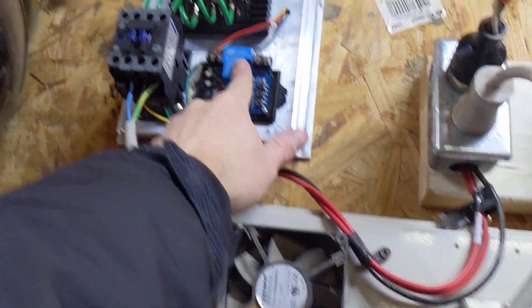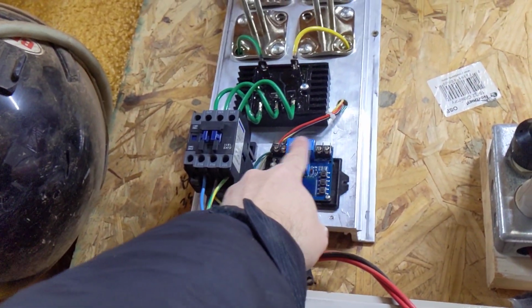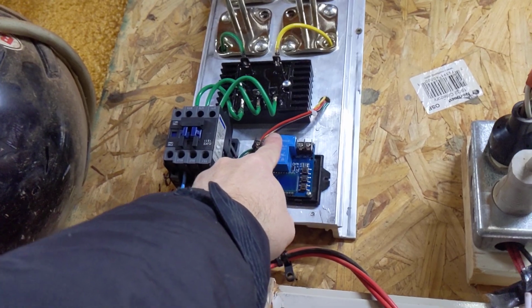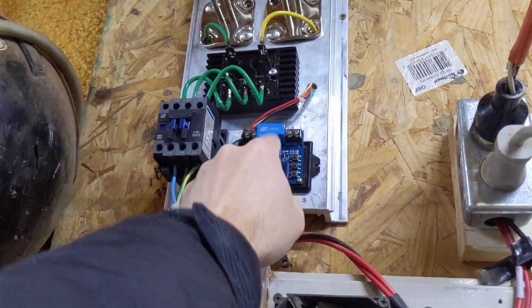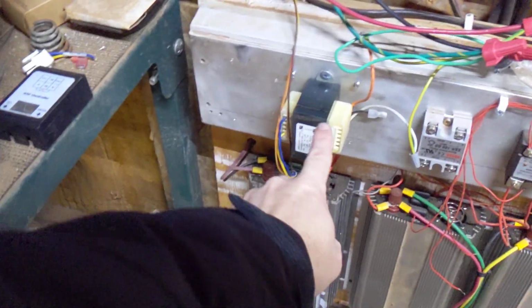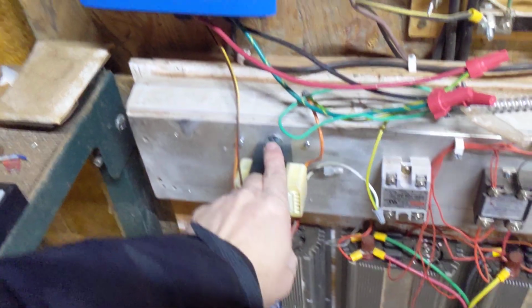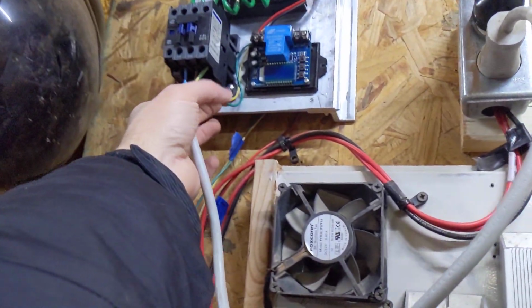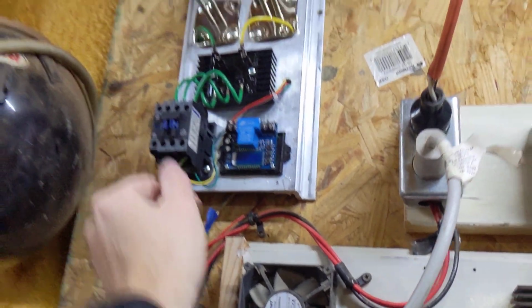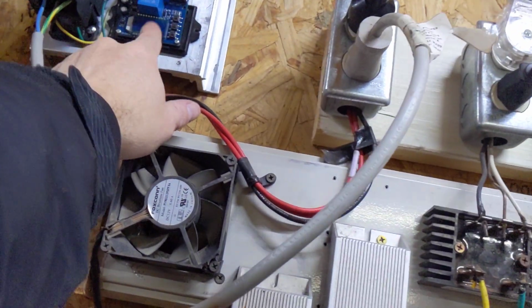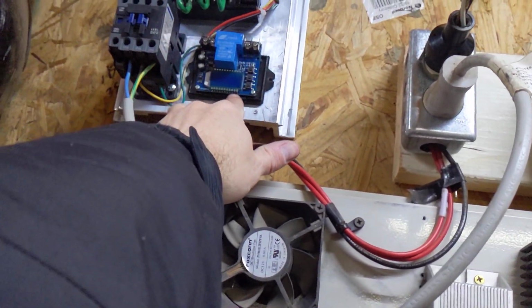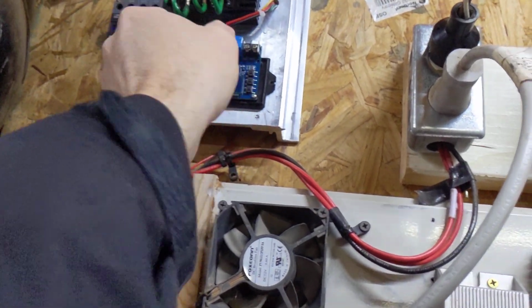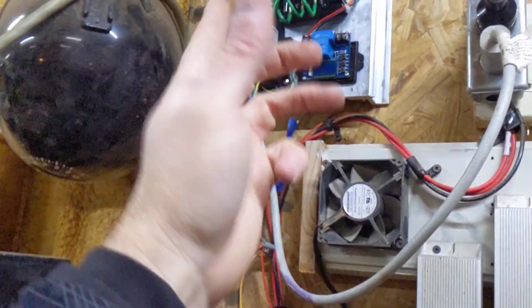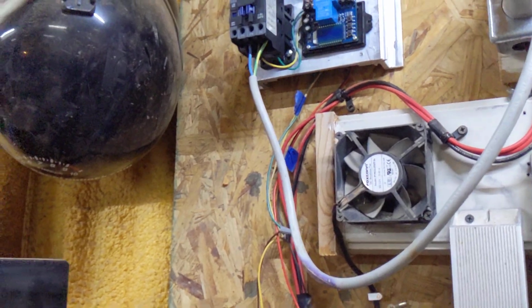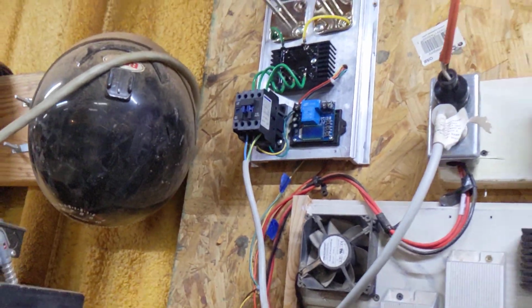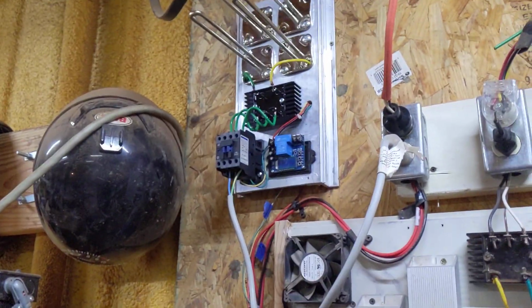I've got this altered to where the cycling circuit is no longer connected to the controller. It goes down to this 24 volt transformer, and then this 24 volt transformer operates this relay. Whenever voltage gets high, this thing is going to trigger, close the relay, and then close the other relay, sending power to all of our resistors.